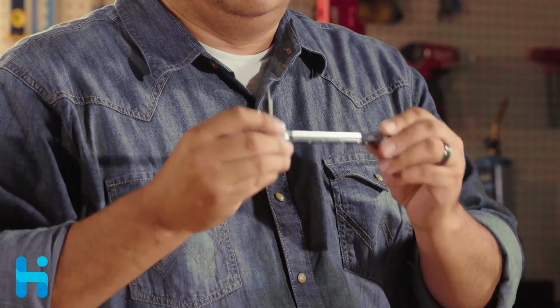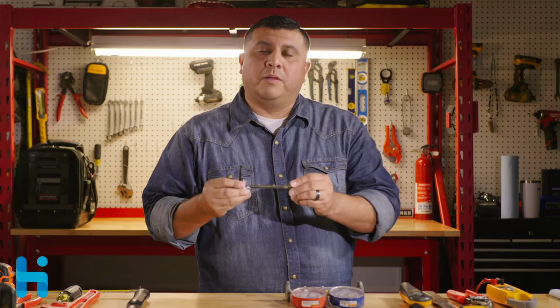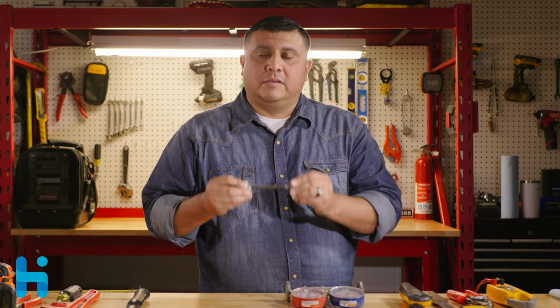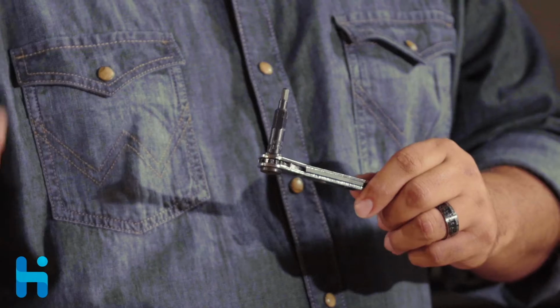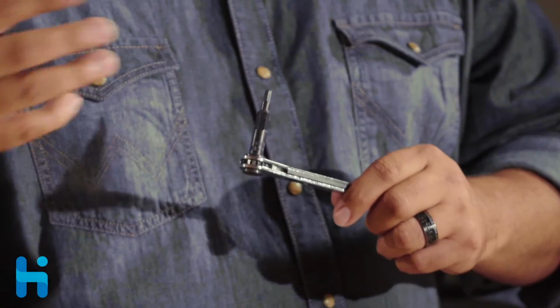For instance, we have the service wrench. We use these when opening up valves on the refrigerant lines. This allows you to close the lines off so you can remove the unit, or if you need to remove a component in a mechanical part of the system, such as a TXV, filter dryer, compressor, or any of those parts, you need to close it off, and this is what we use.